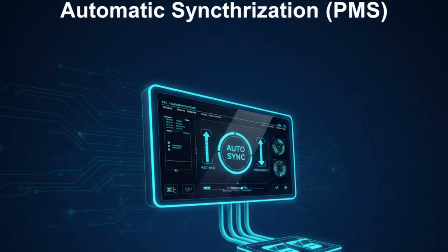Automatic synchronization, PMS. Modern vessels use Power Management System, or PMS. PMS automatically adjusts engine speed, generator voltage, frequency, and phase angle. It continuously compares busbar and incoming generator parameters. When all conditions match perfectly, PMS sends command to close the breaker. This reduces human error and increases safety. It also allows fast load sharing and automatic stop of generators based on load demand. Automatic synchronization is more accurate and faster than manual operation. However, engineers must still understand the basic principle. Because if PMS fails, manual operation may be required. Technology supports us, but knowledge protects us.